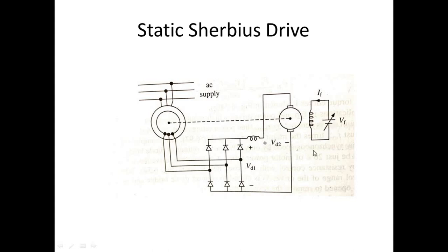In the static Scherbius drive, the recovered slip power is used to drive a DC motor. The voltage Vd2 is controlled by controlling the field voltage of the DC motor. By controlling the field voltage, Vd2 is controlled, and through the slip power recovery scheme, the slip of the induction motor is controlled. These are the two methods of slip power recovery. Thank you.